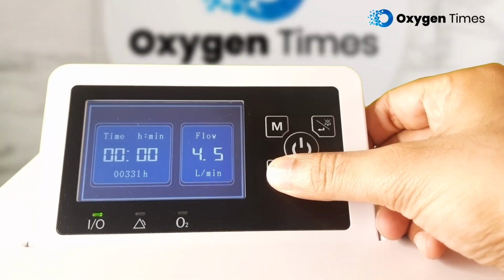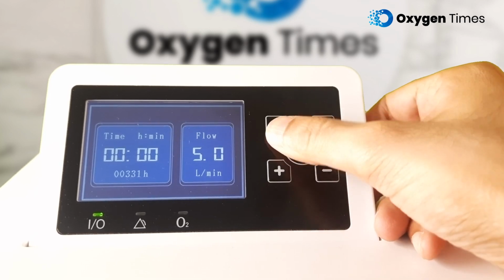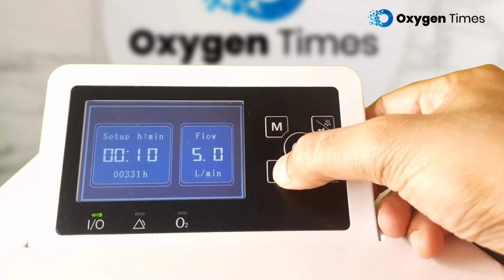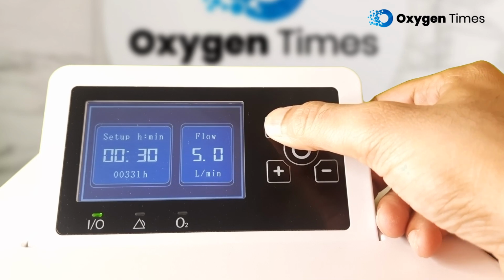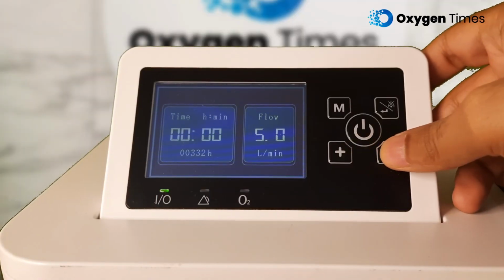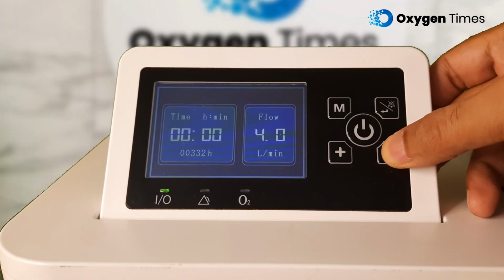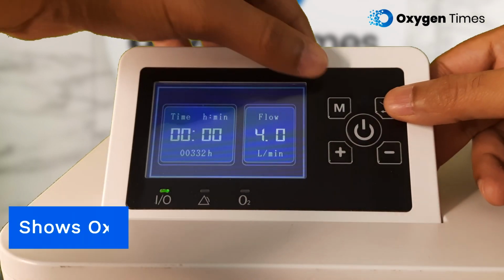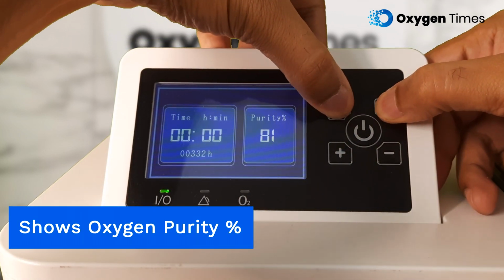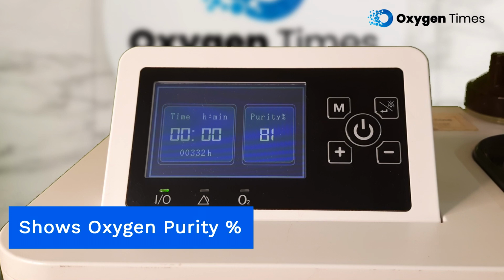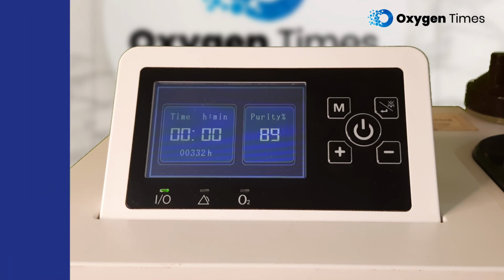The flow rate can easily be set using plus minus buttons, and you can also set the timer in 10 minute intervals up to 5 hours at most. The machine's most impressive feature is that the LED screen can display the oxygen purity level being delivered to the patient in real time. You just have to simultaneously press the top two buttons, and there you go. More about this later in this video.